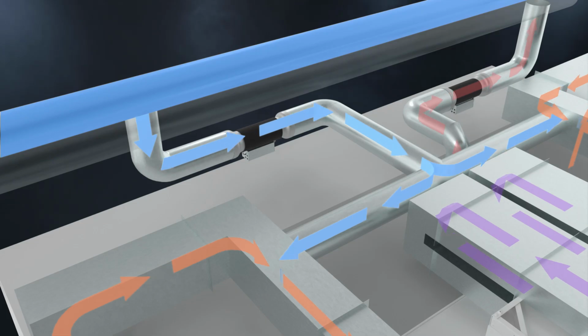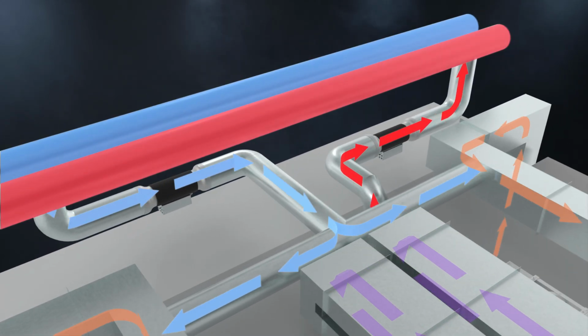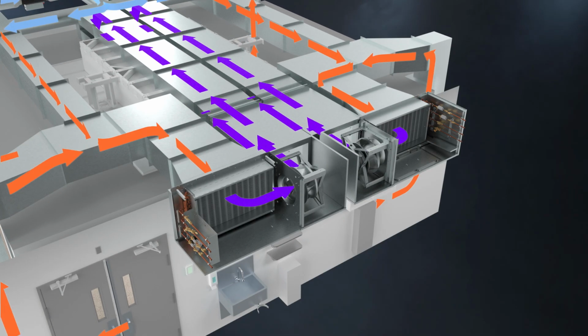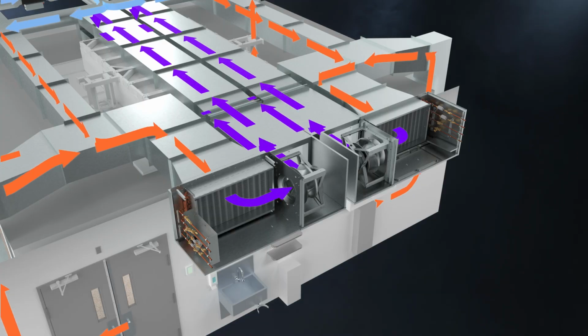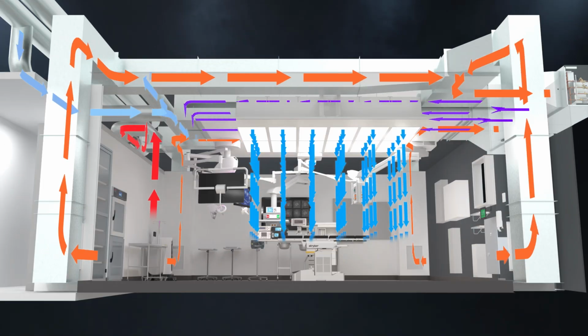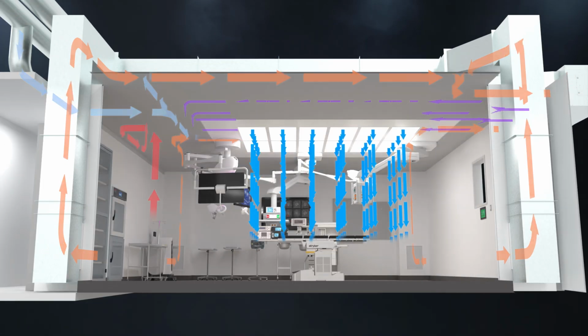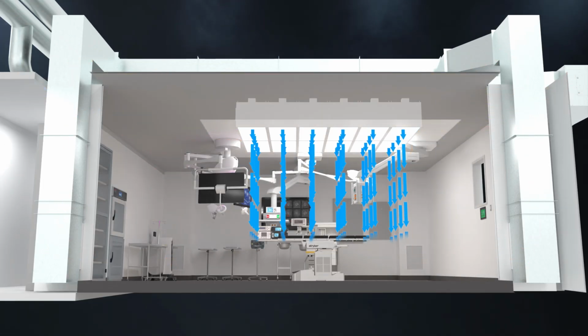Fresh supply airflow and exhaust airflow are managed by a set of airflow control valves that work together to maintain a positive room pressure. The remaining airflow is provided by locally recirculating room air through dedicated fan coil units and HEPA filters. These fan coils provide conditioning for the space and the fan capacity required to reach 60 air changes per hour. Finally, HEPA-filtered airflow is supplied to the operating room through a laminar array that provides a column of clean airflow over the patient table.